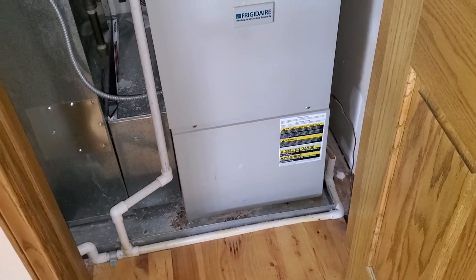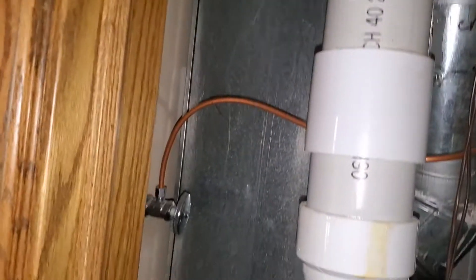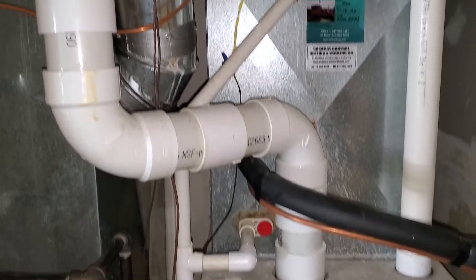Inducer motor is definitely failing. There's tons of rust underneath it. This is a small bypass humidifier. We do have an angle stop. This is supporting the left side of the top floor. Wet pan. Pretty much a twin system of the other one, except this guy has 80,000 BTUs.